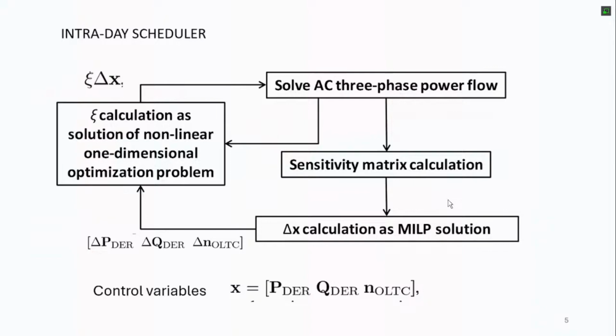So we can solve a problem with a simple structure because it is linear. It is a linear programming problem with some integers, because the number of steps in the transformers is not continuous, so it can be represented by integers, and some other variables can be represented just with a variable that is 0 or 1, not in the middle. In this way, we can calculate, for each 15 minutes, what the adjustments are: how much I need to change the active power, the reactive power, and the tap changers in the transformer in order to achieve a better profile, for example of the voltage or the constraint.